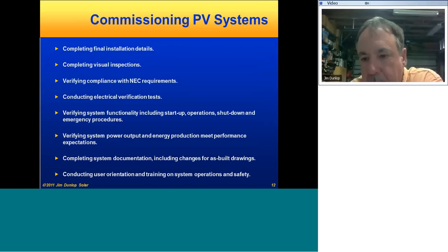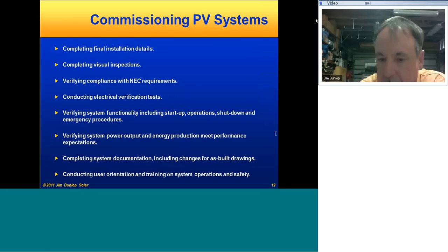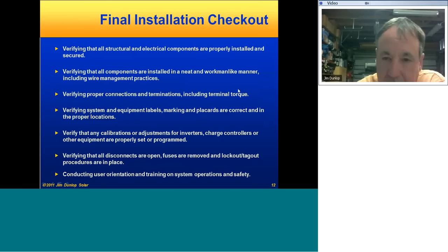So, commissioning systems, I guess there's several aspects to that, both in terms of the technical and administrative details. As far as what you do, obviously you're completing all the final installation details, visual inspections, verifying compliance with NEC, conducting your verification tests, verifying functionality, operation, startup, shutdown, safety and emergency procedures. You're going to try to update any of the documentation as needed, drawings to as-built status, and any kind of training to the user on the orientation of the system, operation, safety, that sort of thing, could be done as part of that commissioning. So the first things you usually do are final installation.